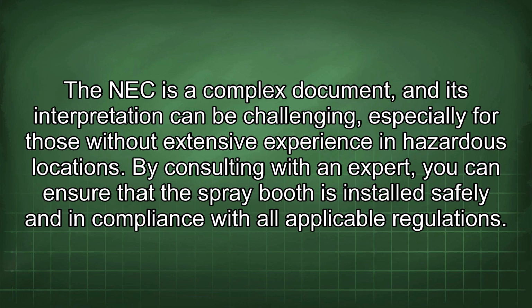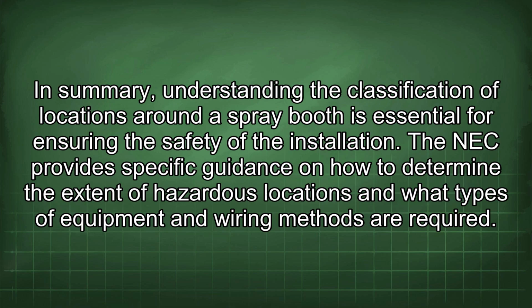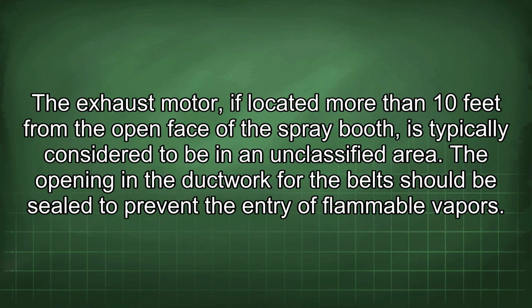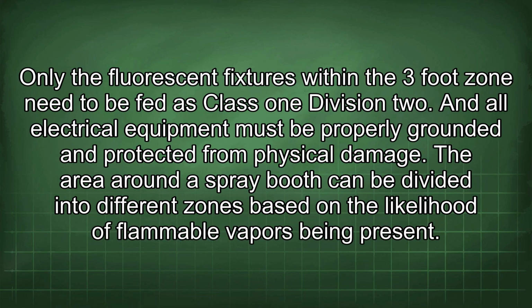In summary, understanding the classification of locations around a spray booth is essential for ensuring the safety of the installation. The NEC provides specific guidance on how to determine the extent of hazardous locations and what types of equipment and wiring methods are required. The exhaust motor, if located more than 10 feet from the open face of the spray booth, is typically considered to be in an unclassified area. The opening in the ductwork for the belts should be sealed to prevent the entry of flammable vapors. Only the fluorescent fixtures within the 3-foot zone need to be fed as Class 1 Division 2. And all electrical equipment must be properly grounded and protected from physical damage.